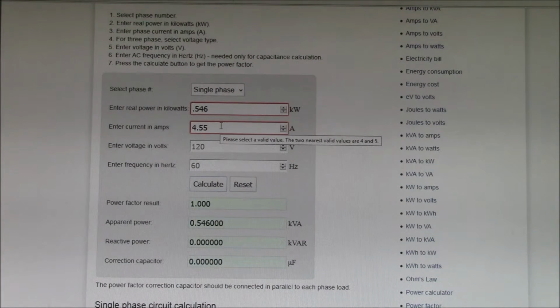I haven't had to increase my inverter size, I haven't had to add solar panels or charge controllers, just the price of a capacitor. The conventional wisdom is that power factor really doesn't matter for residential loads because you're not billed for the reactive power that you consume, because it's not real power. If you were to run this washing machine for an hour, you would be billed for 0.546 kilowatt hours. The apparent power is over 1,000 volt amps, but you're not billed for that.